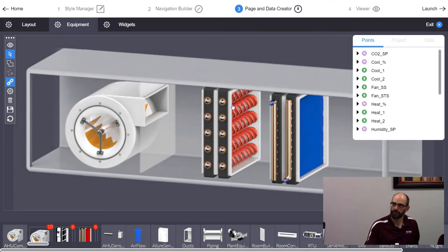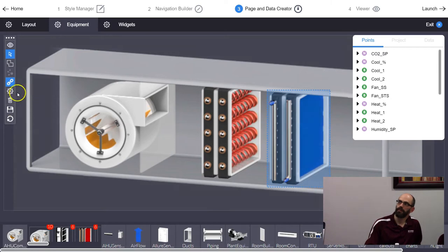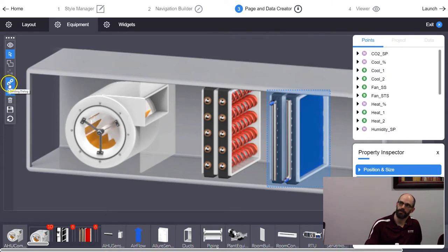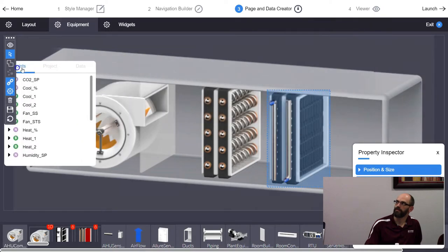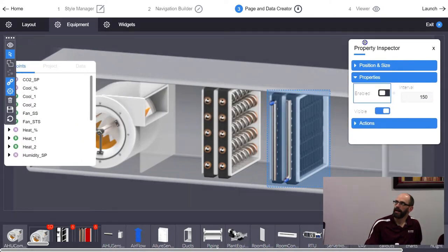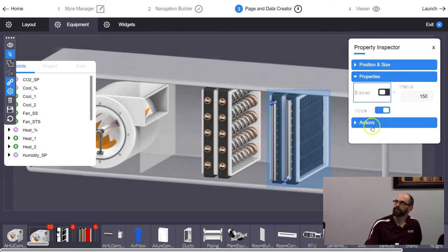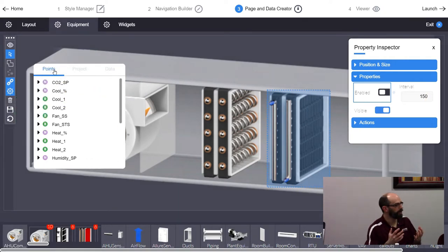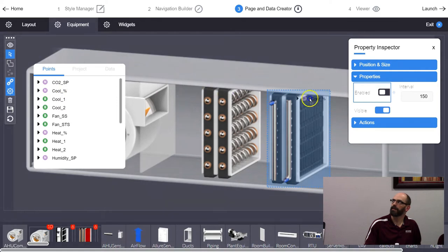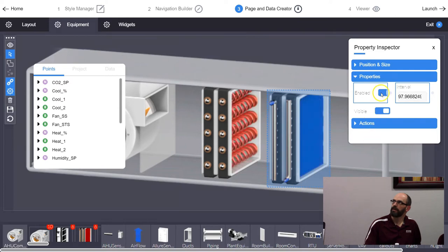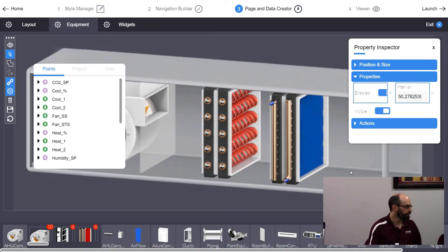You can go deeper on each element by clicking the gear icon next to it. The gear shows information about that element. For example, on the cooling coil I can take the cooling percentage and link it to the interval. So now the animation interval is dynamically changing — it'll flash faster as that number goes up and slower as it goes down. You can also link visible, enabled, and interval separately. Everything in DG Lux can be linked to something else.